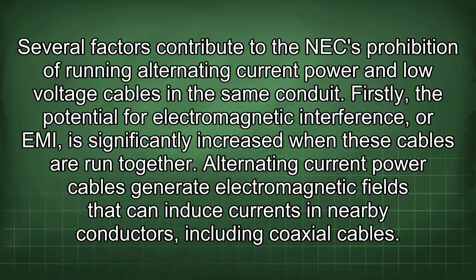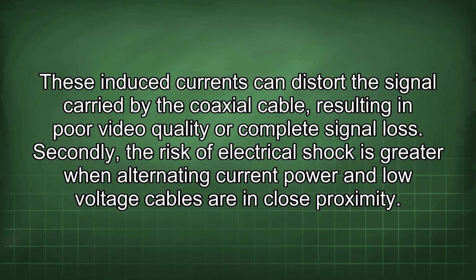Several factors contribute to the NEC prohibition of running alternating current power and low voltage cables in the same conduit. Firstly, the potential for electromagnetic interference, or EMI, is significantly increased when these cables are run together. Alternating current power cables generate electromagnetic fields that can induce currents in nearby conductors, including coaxial cables.